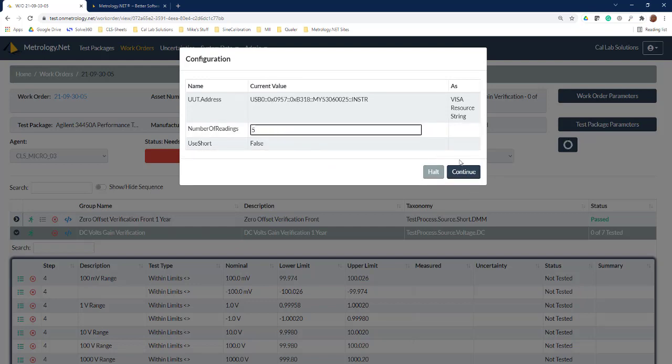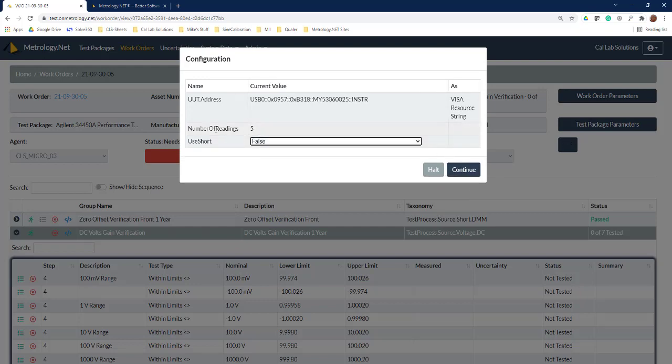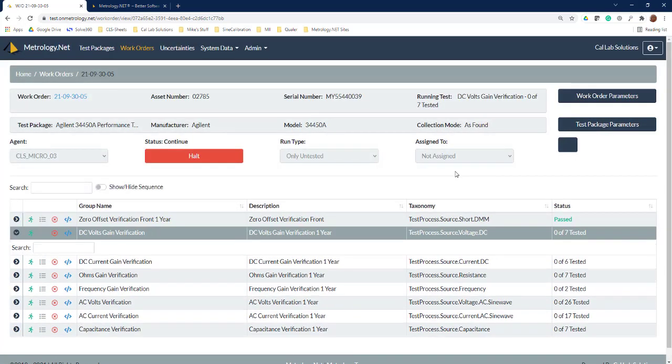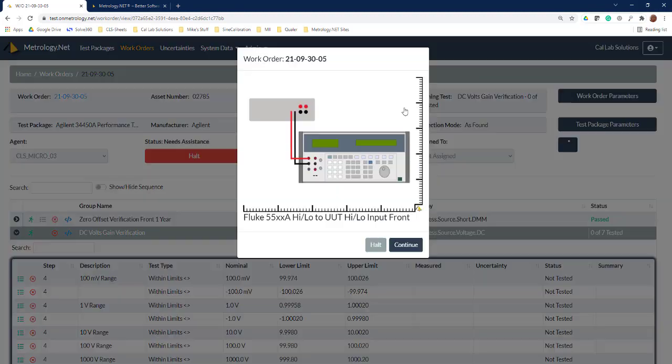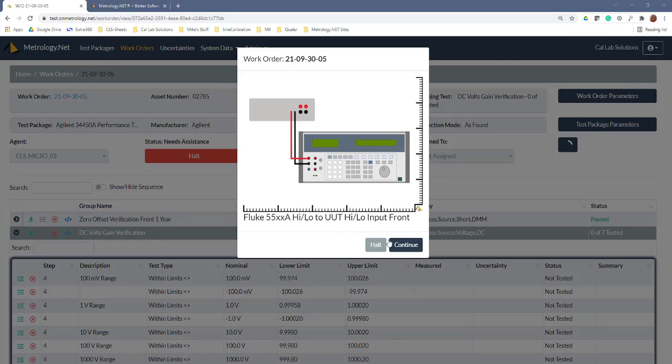We'll go ahead and say we want to do five measurements at each data point. We don't want to use a short because we have no zero points—but this short feature, what this does is if it's a zero point, has us connect the short. If we don't use a short then it will use the calibrator to generate the zero volts. Now we'll hit continue. It's going to reset the calibrator, reset the unit under test. Now we get our connection message.